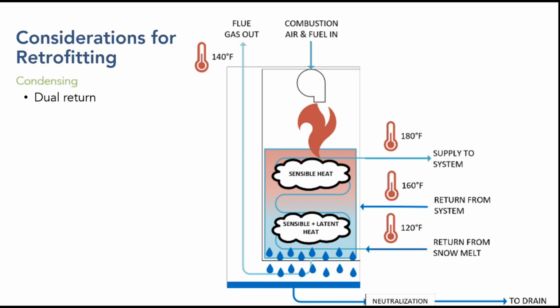Again, we are not recommending any particular technologies for different manufacturers. I have heard the knock on this type of system that it introduces unnecessary thermal stresses in the boiler, and maybe you have to have a pretty consistent return temperature on your alternate process for this to happen. So, it's something to be evaluated.